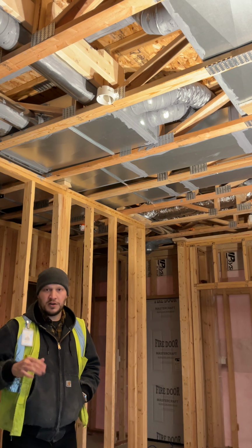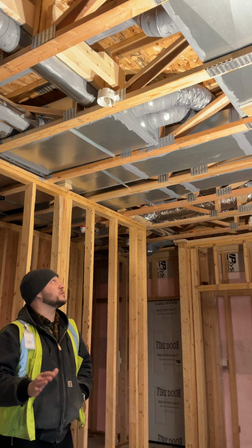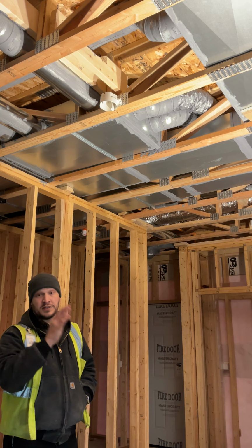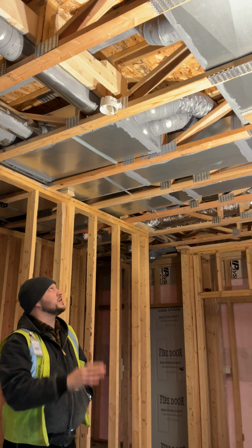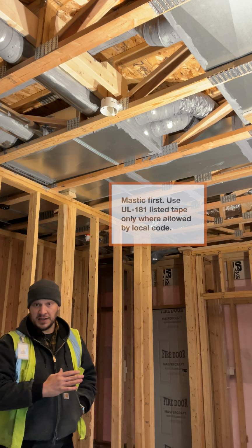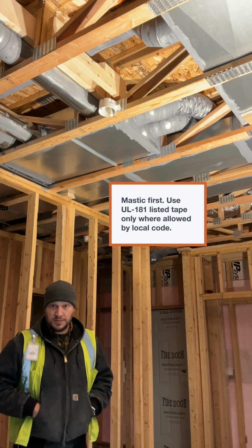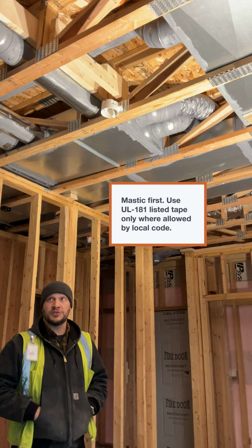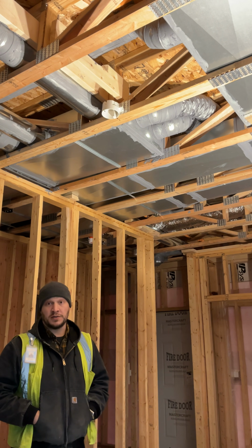So air seal early and often. You should visually inspect all your ductwork before drywall goes up, making sure you have airtight seals across all seams. You can see here they've used mastic, which is painted on. You can also use various tapes or aerosol sealant, but all ductwork should be sealed before drywall is completed.